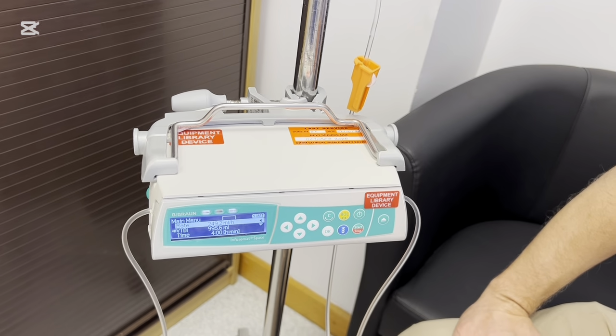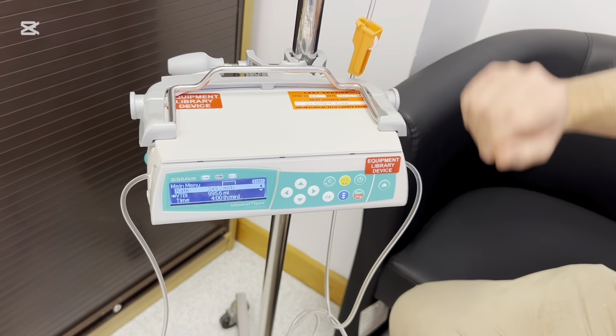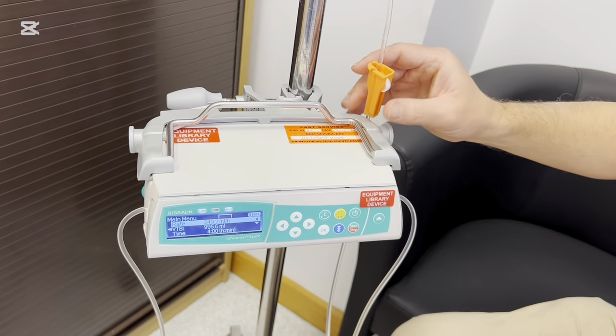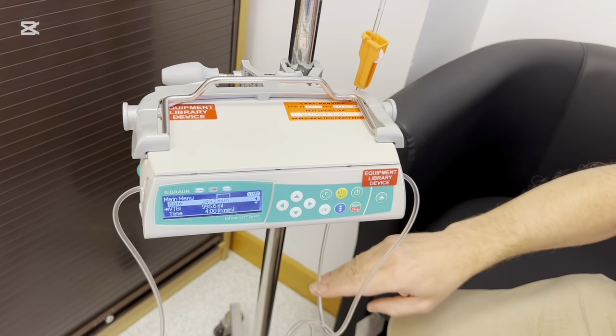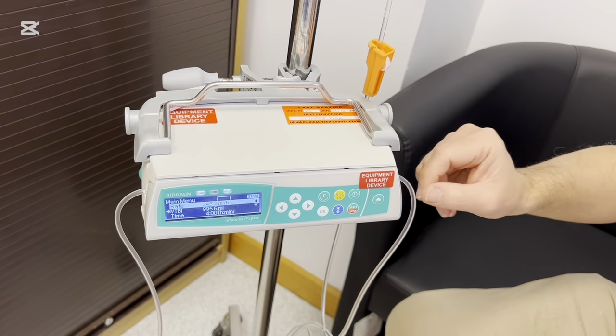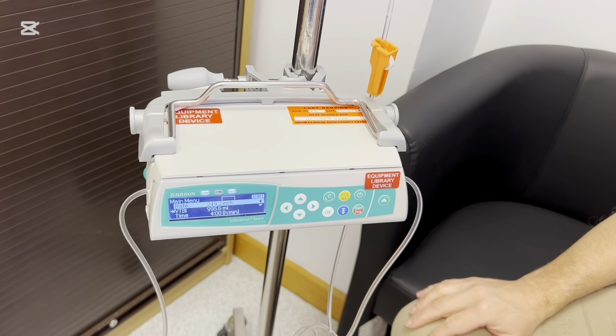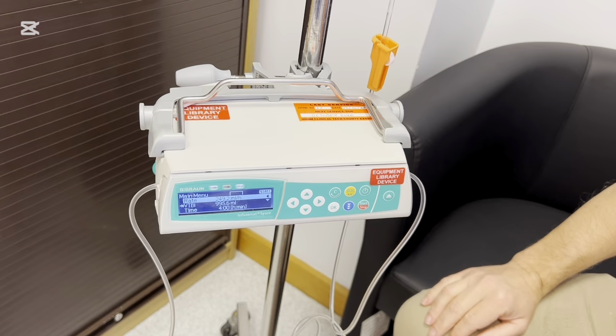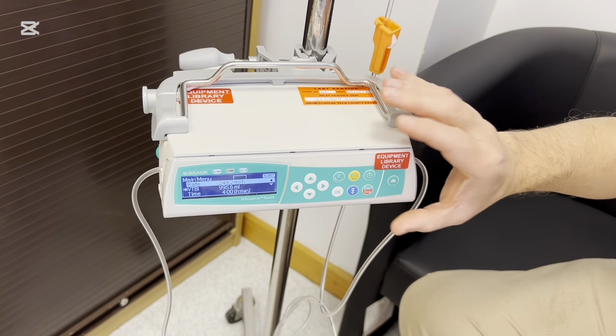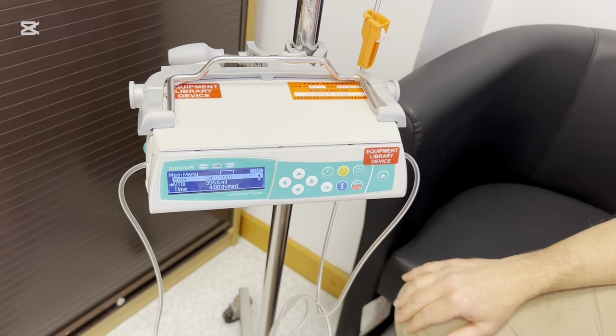Important notes to mention when these pumps come from the wards is that it's important to pause the pump, close the roller clamp so that air doesn't get into the pumping segment or into the fluid line, because once you get air into the fluid line then it's very difficult to clear it and you end up with countless alarms. And hopefully if you follow those simple rules you shouldn't have too many problems with this device.